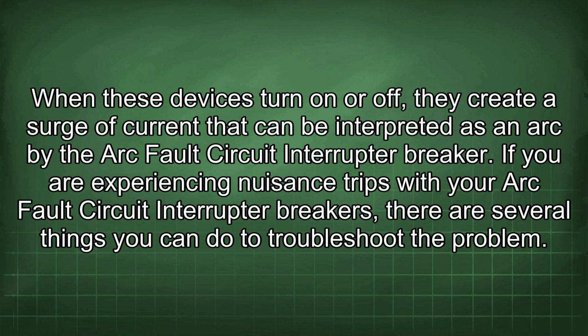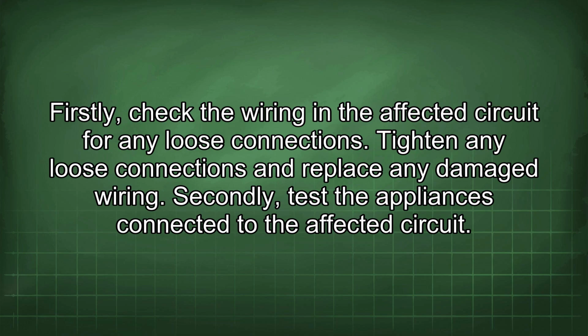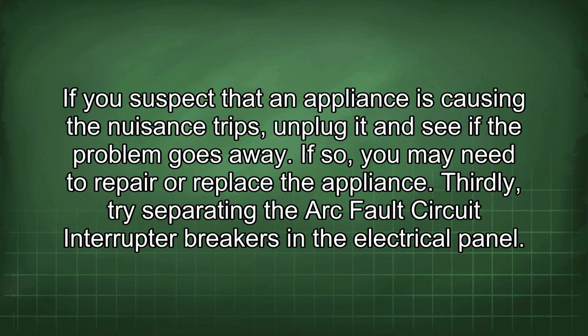If you are experiencing nuisance trips with your arc fault circuit interrupter breakers, there are several things you can do to troubleshoot the problem. Firstly, check the wiring in the affected circuit for any loose connections. Tighten any loose connections and replace any damaged wiring. Secondly, test the appliances connected to the affected circuit. If you suspect that an appliance is causing the nuisance trips, unplug it and see if the problem goes away. If so, you may need to repair or replace the appliance.